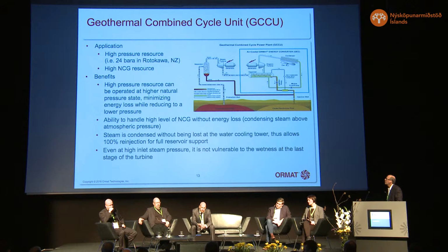The benefits are that with the high pressure, we can use the energy of the high pressure steam without having any excessive wetness at the last stages of the steam turbine. The NCG is released to the atmosphere at above atmospheric pressure, so there is no need for any energy to dispose the NCG. Since the bottoming unit can be air-cooled, there is a 100% reinjection of the steam condensate and the brine back to the earth.